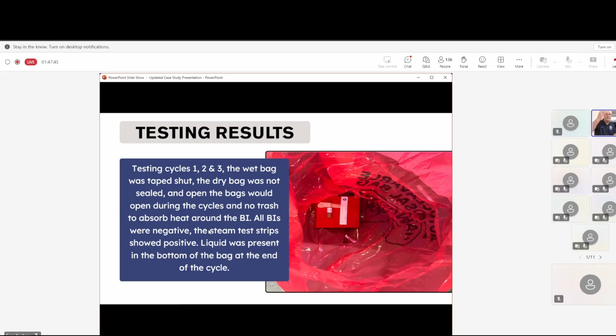And then on the outside, I put another steam strip on the outside and one on the inside along with the BI. Next slide, please. This is what the bags look like inside and on the BioPro 300. One bag, I had one that was sealed with liquid in it. I had another dry bag. I left it open and closed. You can see where it just had that in it, and that's what I used for cycles 1, 2, 3.